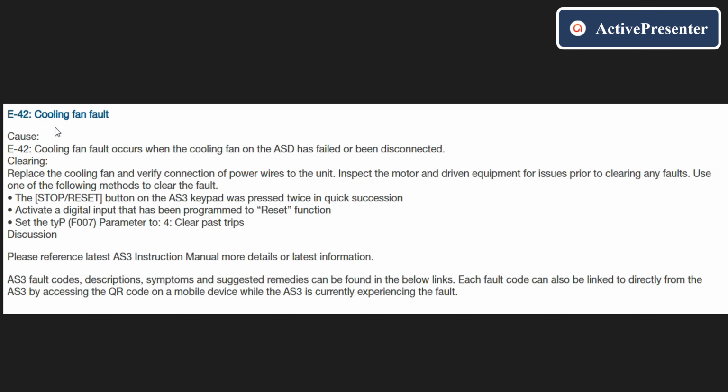So we will talk about there is an E-42 error, cooling fan fault. Cooling fan fault occurs when the cooling fan of the ASD has failed or been disconnected. Inside of the VFD, there is a fan. What is it doing? It is just dissipating the heat.